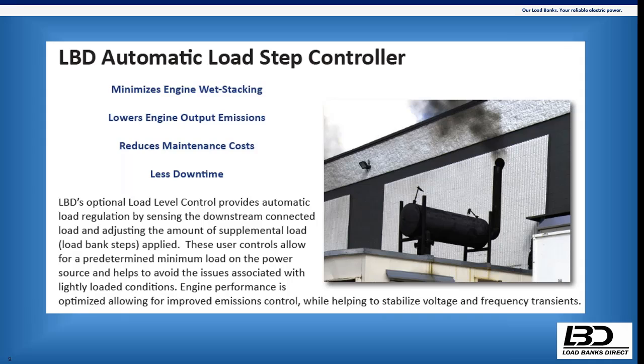And the big pro of that is it's automatic, and nobody has to be monitoring this all the time, as long as it's set correctly when it's installed and set in the right mode. It monitors nonstop whenever the generator's running, and does that automatically. It ramps up, it ramps down.